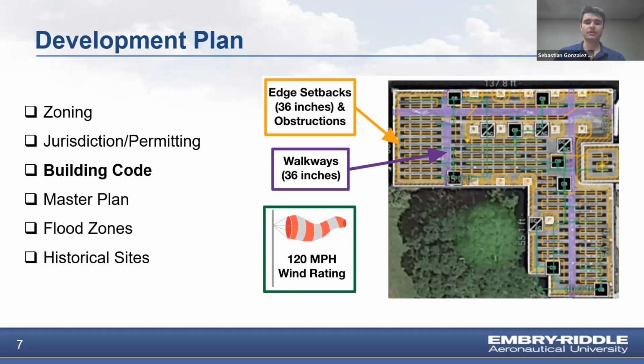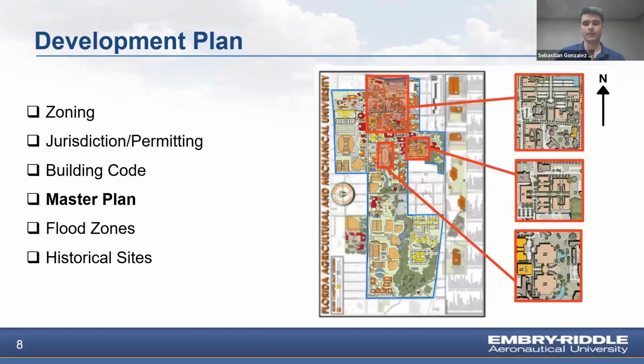Now, being in the state of Florida, all construction is subject to the Florida Building Code. For PV systems, Florida Building Code requires 36-inch edge setbacks, 36-inch walkways for large panel clusters, and a 120 mile-per-hour wind rating. All our PV systems were designed to comply with the rules. Our allied health building design is an example of this. The edge setback is shown in orange, and the walkways are shown in purple.